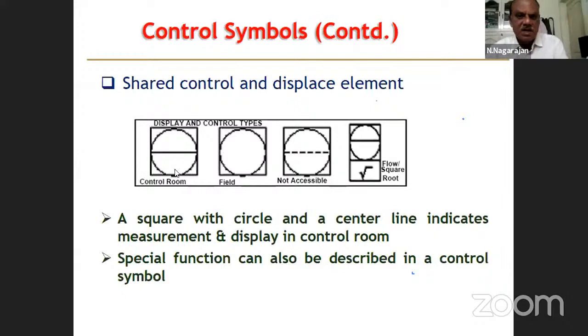A shared control and display element means displayed and control types. It is displayed in the control room. A circle inside a square with a center line. And if you have the same field instrument with the DCS connected, this is the circle in a square, and again this is behind the panel. You can remember: line means control room, no line means field, dotted line means behind the panel or not accessible by the operator, but instrument technicians have to access it and do the repair work or maintenance. This is behind the panel where people normally won't go.